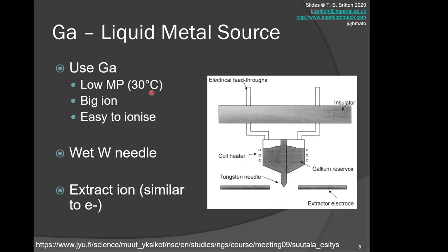Why do we use gallium? Gallium is very common for a FIB. Effectively, it's a low melting point material—it will melt in the palm of your hand. That's very useful because you can use this to wet the surface of a sharp tungsten needle, and then if you have an extractor electrode, you can rip off ions from that liquid metal and replenish from your metal source. It's a relatively big ion, which means it has relatively good sputtering efficiency, and it's relatively easy to ionize and extract.